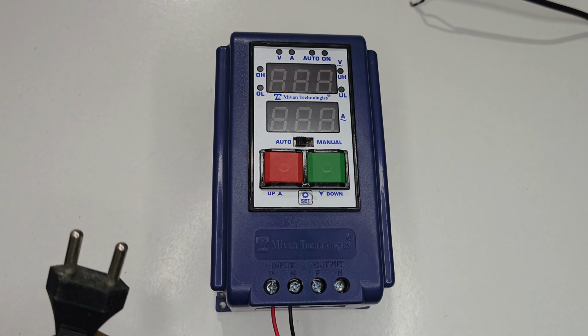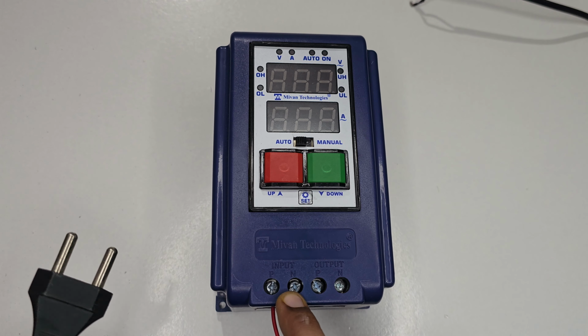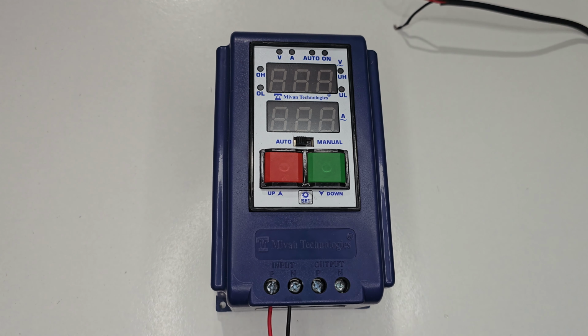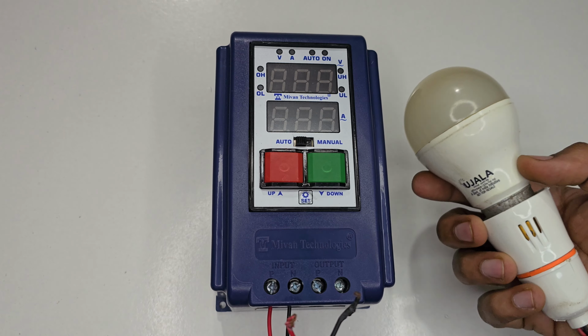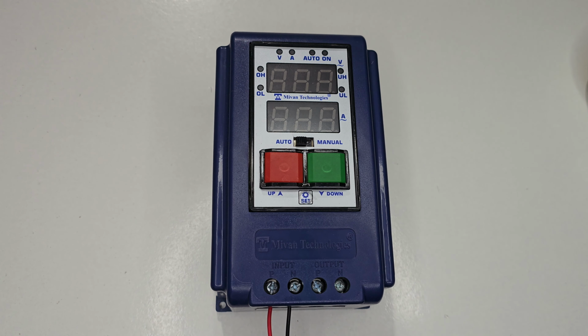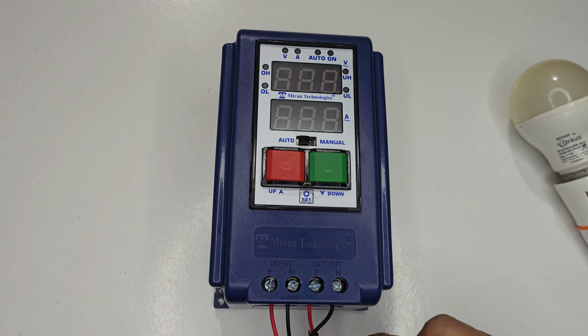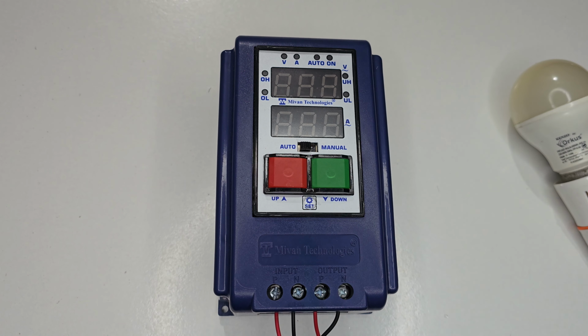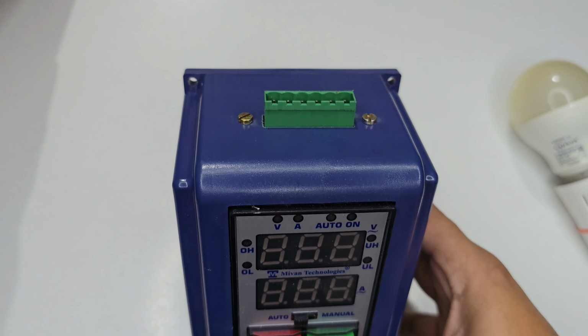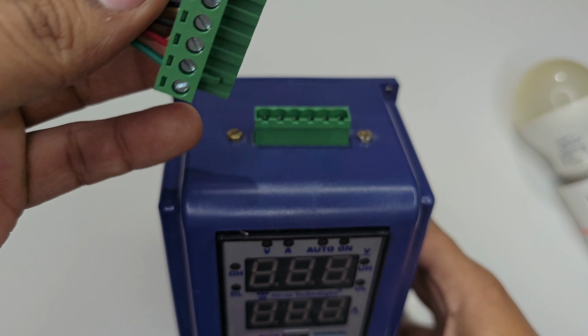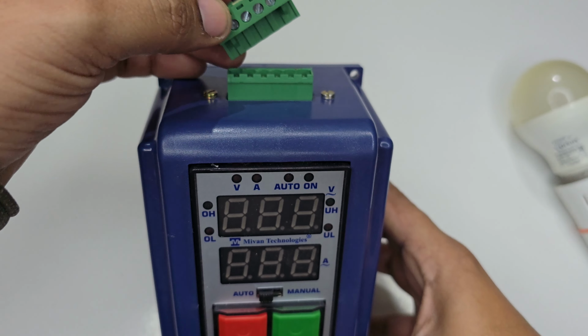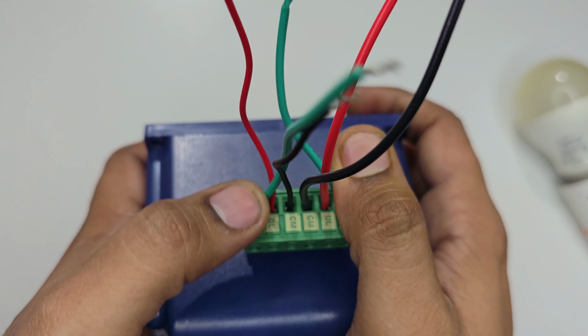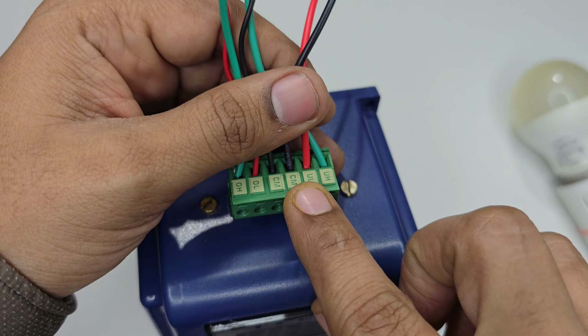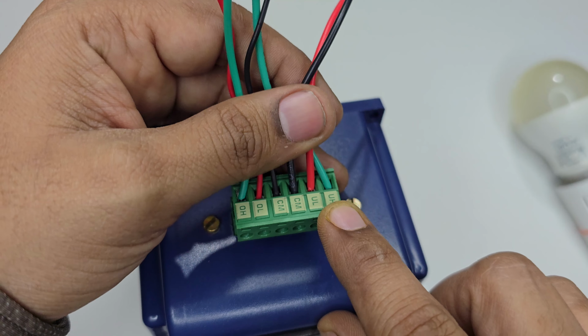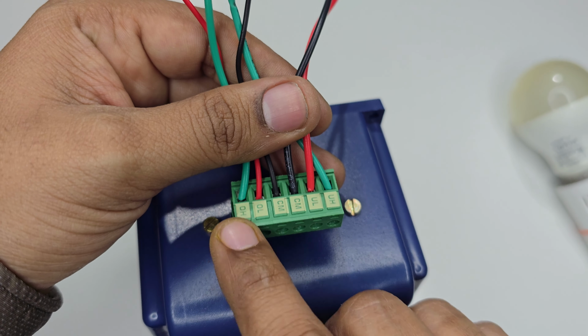You need to connect the 2 wires of the supply cable at the input terminal and you need to connect the motor at the output terminal, but for testing purposes I am connecting the 2 wires of a bulb. Now I have connected the 2 wires of a bulb at the phase and neutral output of this device. At the sensor terminals, you need to connect 6 sensors. But instead of sensors, I have connected small pieces of wire for testing purposes at the sensor terminals. You need to put the 3 underground tank sensors C, UL and UH in the underground tank, and the 3 sensors C, OL and OH in the overhead tank.